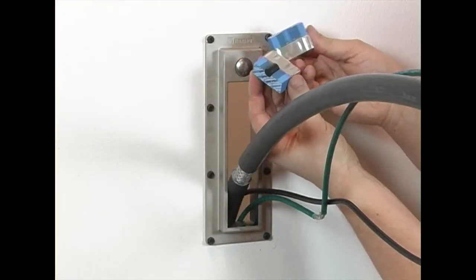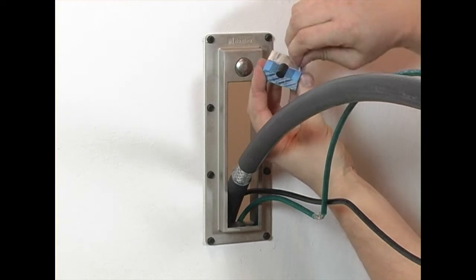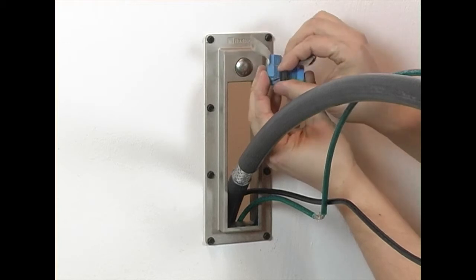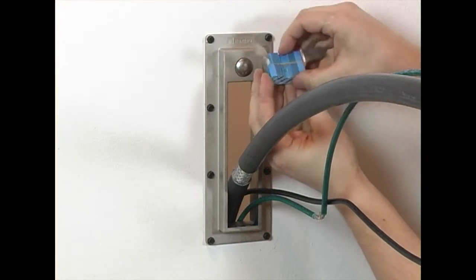Adapt the modules to the correct dimension, both for the cable sheath at one end of the module and for the cable screen at the other. Do this by peeling off layers from each module half.